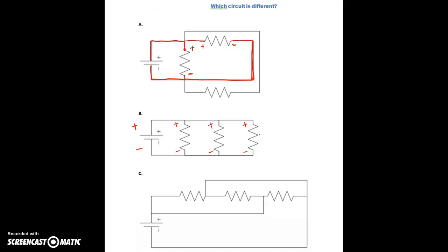Last one, let's take a look. This is our negative here, so that ties into this side of the resistor. And then let's see if this guy is going to be positive. I'm just putting positive there, but if we follow this guy back from here over here, oh very nice, goes back to the positive of the source. So these one look totally different, but in fact they're the same. Okay, again, when you're doing your ladder diagrams for shop and everything, you'll have a number of different people come up with different circuits. They will work exactly the same way, but they'll be written or drawn completely differently.